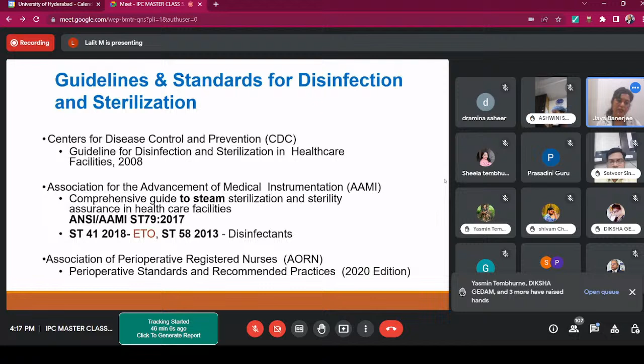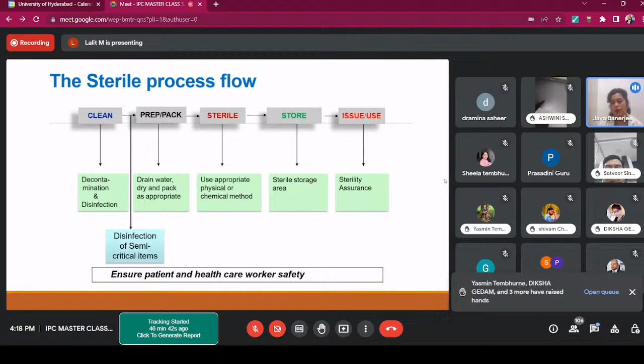Next, please. So particularly the sterile flow process: first is decontamination in the CSSD, and next is inspect and pack, drain water, dry and pack as appropriate. Then disinfection of the semi-critical items, sterilize using appropriate physical and chemical methods. This is very important. We will talk about it later. And then store in the sterile storage area and issue wherever required, in the OT, the ward or the ICUs. The small packs we use are sent from the issue areas. Next.